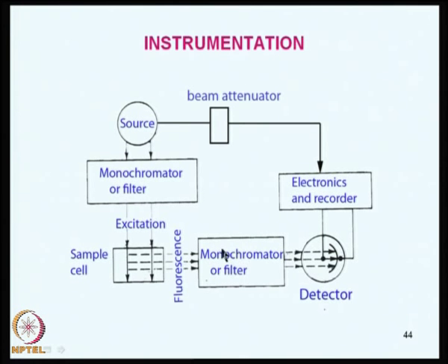That means, if the incident radiation is coming vertically, I must have a provision to make the measurement horizontally. And then how do I measure? Here I need the emission wavelength. That means I have to put one more monochromator or filter, and that wavelength would be different from the excitation monochromator.